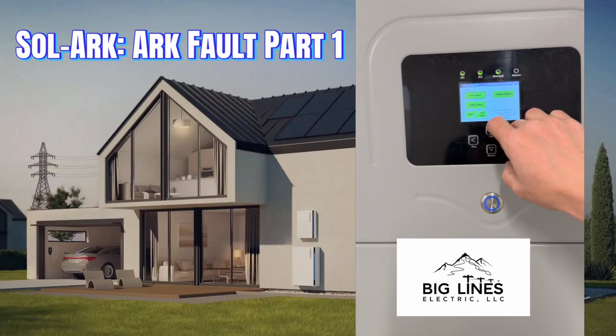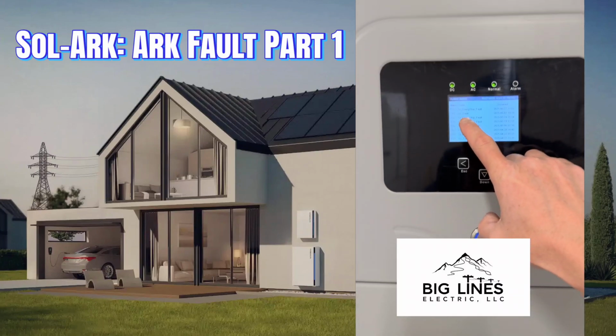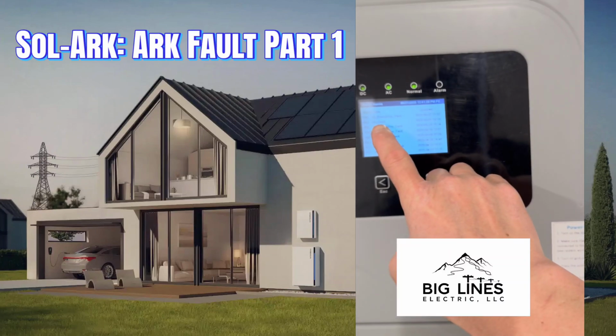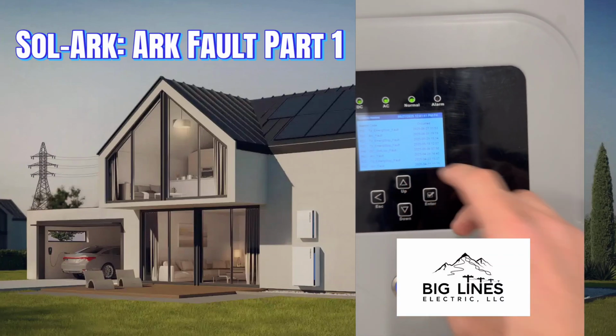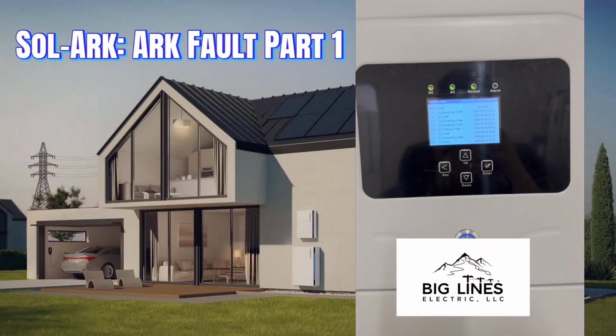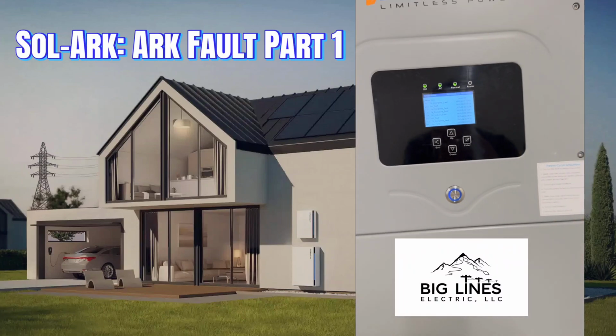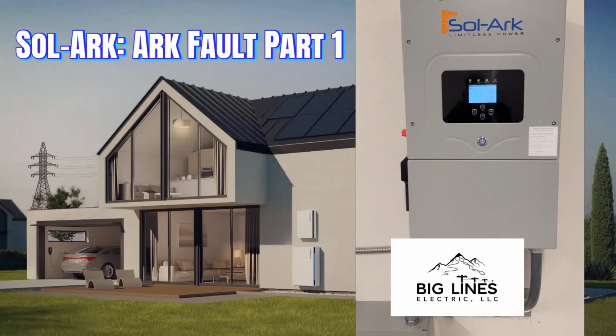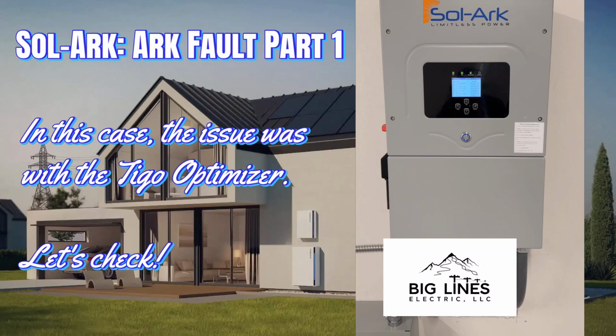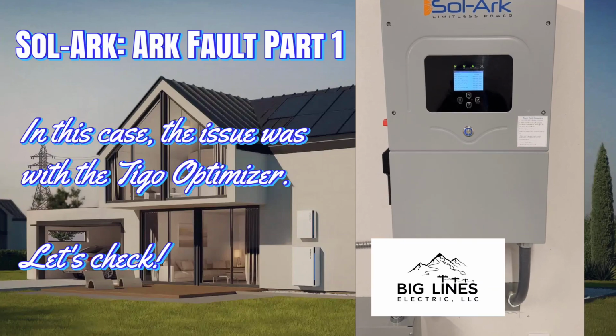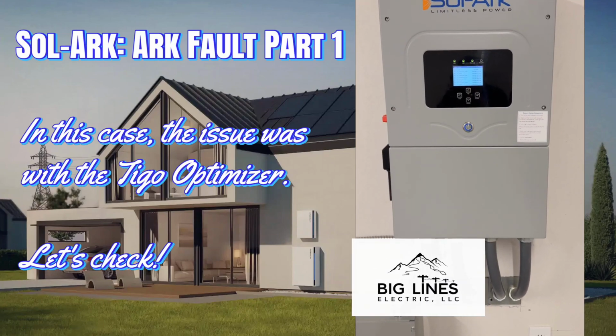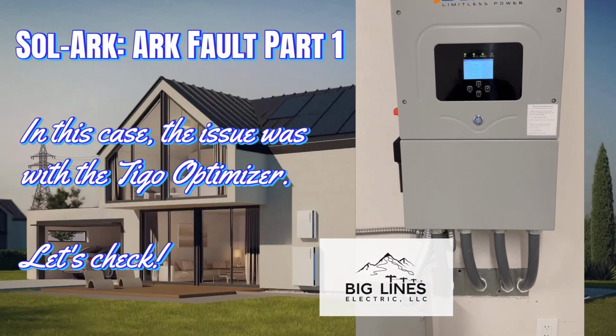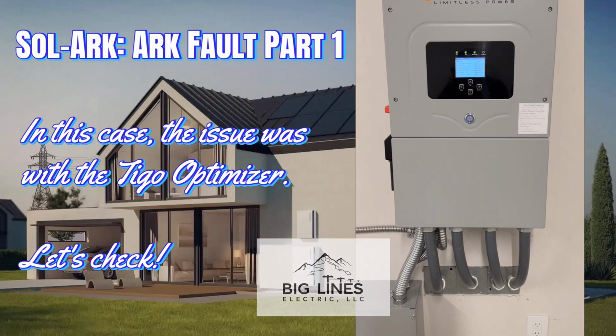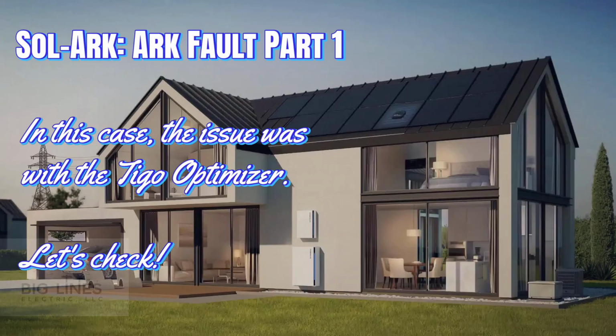You go to the wheel, alarm setup, and here you can see that I got a few arc faults, and I've been troubleshooting that for probably about 3 months now, dealing with Sol-Ark and Tigo on this problem. And what we found was it's the Tigo Optimizers. Let me take you up there and I'll show you what those are and explain what's going on.